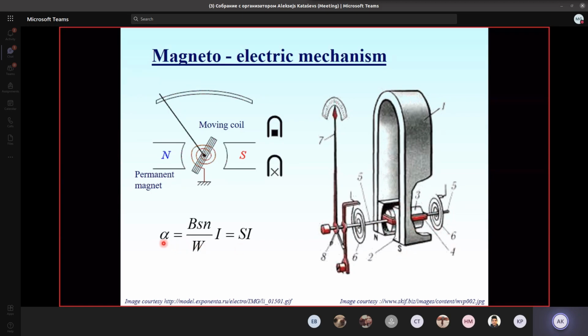The relationship between the deflection angle and the current flowing through is linear, and the coefficient is defined by the magnetic field strength inside the coil. So this magnetic induction value B, the cross section area of the coil S, the number of turns in the coil N, and W is the stiffness of the helical springs, the angular stiffness actually. So the deflection angle is proportional to the current, because the field is constant. Yes, the deflection is proportional to the current.